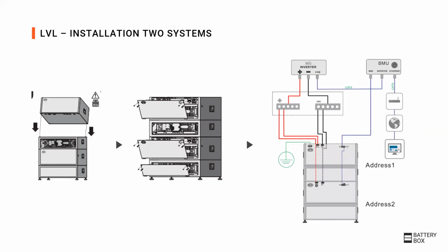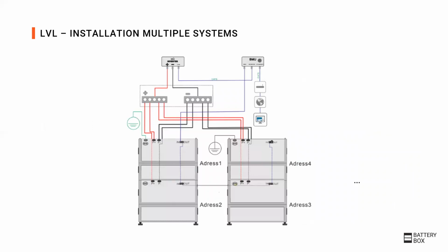Up to 2 LVL can be stacked on top of each other. The cabling concept is shown on the right side. The LVLs are connected with the Cat5 or higher cable, and the LVL with address 1 is connected to the BMU. To collect the DC cables, make sure to use a combiner box or a busbar. The same concept is used when connecting more LVL systems in parallel.